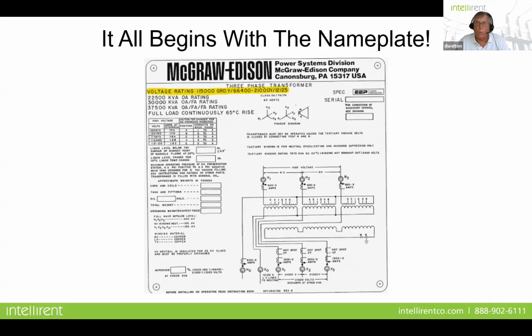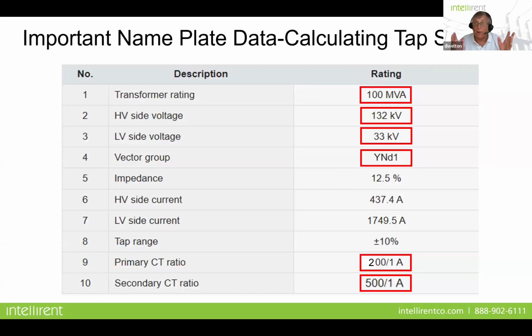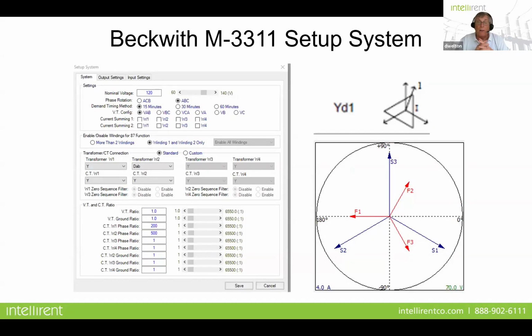Okay, so what information do we look at in the nameplate for setting a differential element? Well, we look at the transformer rating, 100 MVA. We look at the high side voltage. We look at the low side voltage. We look at the vector group, so we know how to compensate for that phase shift. And we use the primary and secondary CT ratios to set the differential relay. And how do we use that information? Well, it's quite simple. Here is the setting for the Beckwith relay.